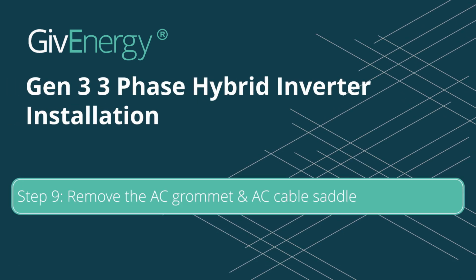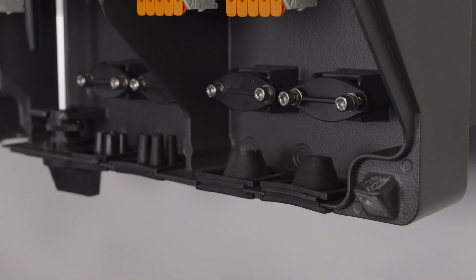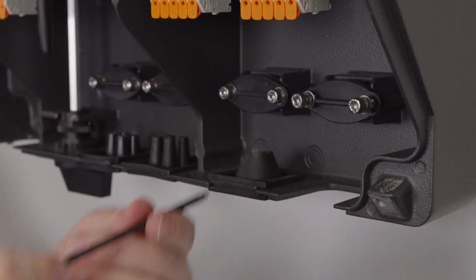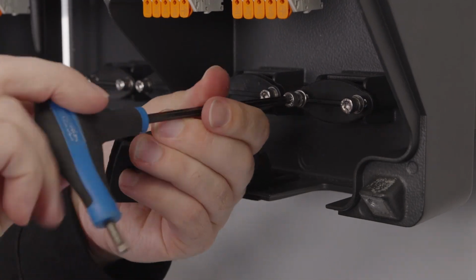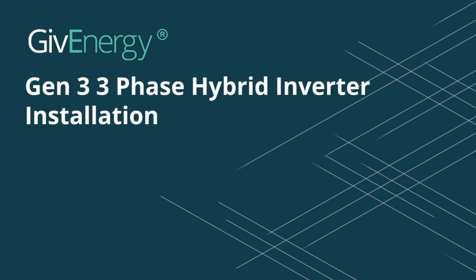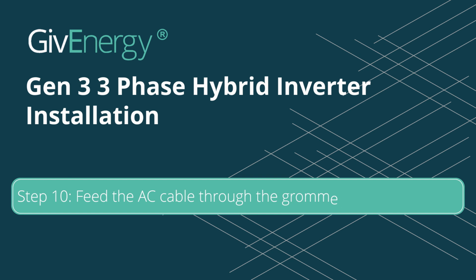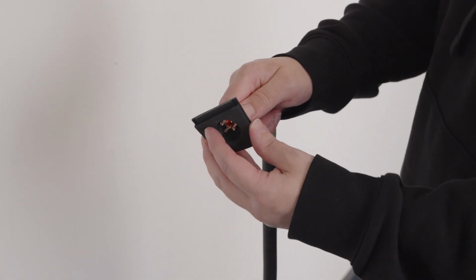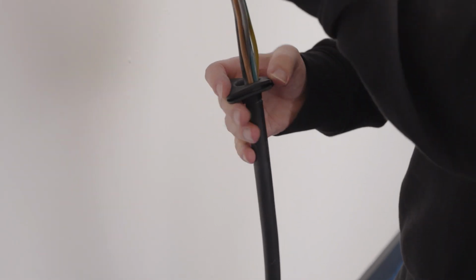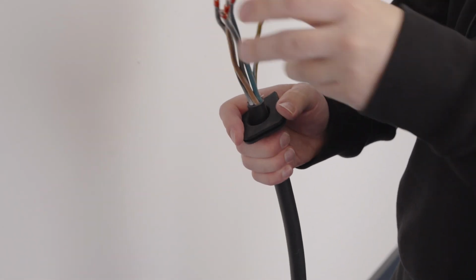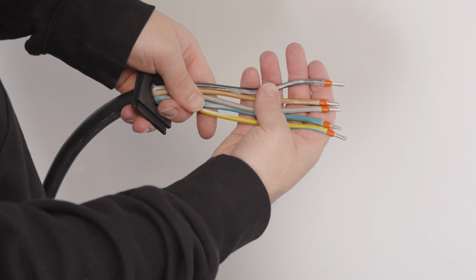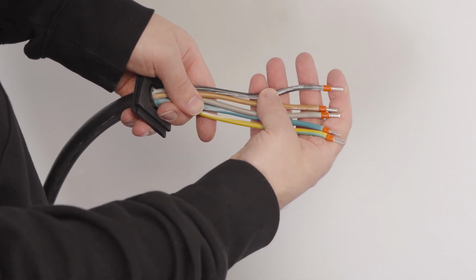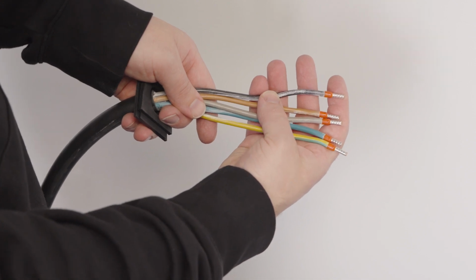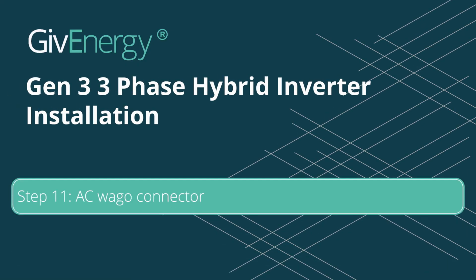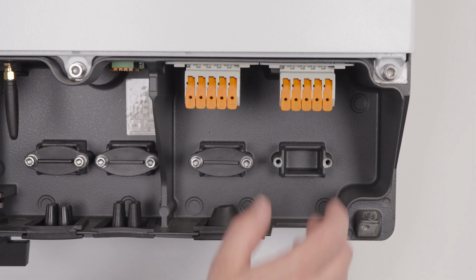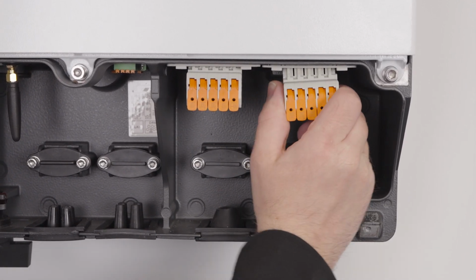Step 9. Remove the AC grommet and AC cable saddle. Simply remove the rubber grommet out of the way and then unscrew and loosen the cable saddle above the rubber grommet. Step 10. Feed the AC cable through the grommet. Now feed the cables through the grommet. Strip the cables using your wire stripper so that the appropriate amount of exposed conductive material is visible on each cable. Use bootlace ferrules where possible. Step 11. The AC Wago connector. To make installation easy, remove the lever arch plug.